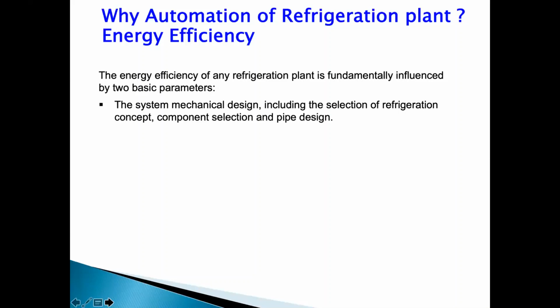When we talk about performance and safety, we talk about efficiency. Efficiency can be implemented right from the designing of the plant by selecting the components, considering the plant operation, location of the plant, and how the plant is going to be operated. Some of the places you find the cold storage is loaded in 2 months and then kept locked for 4 months and starts unloading after 4 months. Whereas in some cases, the cold storages are particularly close to the big cities like Chennai, Mumbai, and are operated on a daily basis. There is a loading and unloading every day.